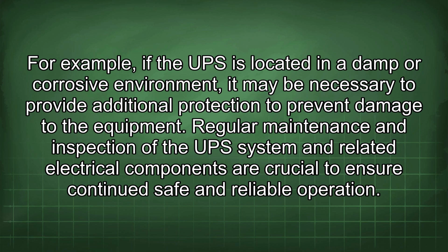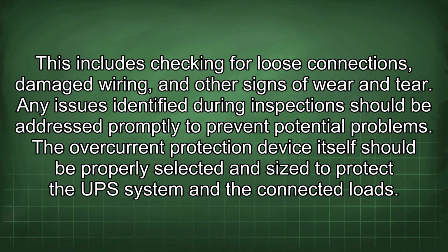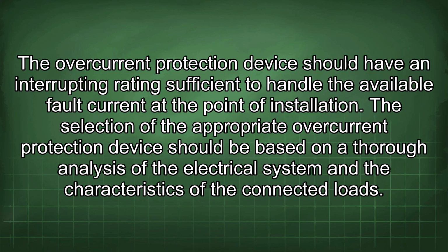Regular maintenance and inspection of the UPS system and related electrical components are crucial to ensure continued safe and reliable operation. This includes checking for loose connections, damaged wiring, and other signs of wear and tear. Any issues identified during inspection should be addressed promptly to prevent potential problems. The overcurrent protection device itself should be properly selected and sized to protect the UPS system and the connected loads. The overcurrent protection device should have an interrupting rating sufficient to handle the available fault current at the point of installation. The selection of the appropriate overcurrent protection device should be based on a thorough analysis of the electrical system and the characteristics of the connected loads.